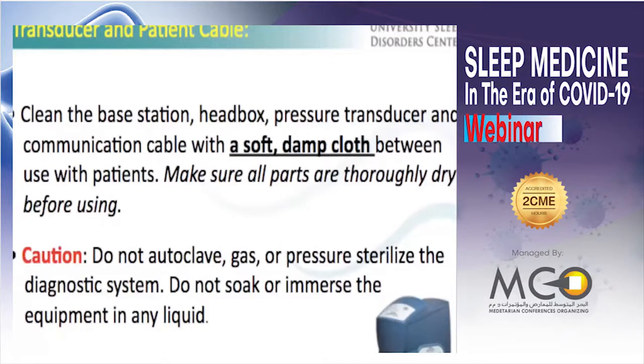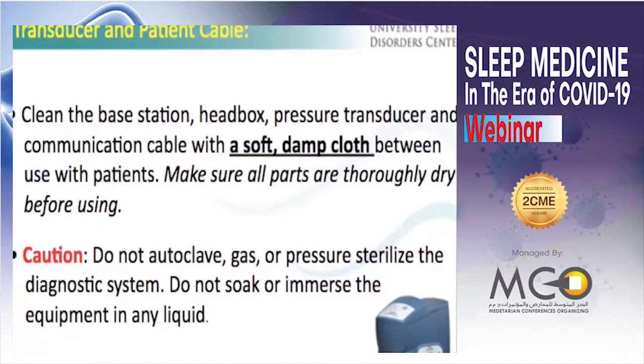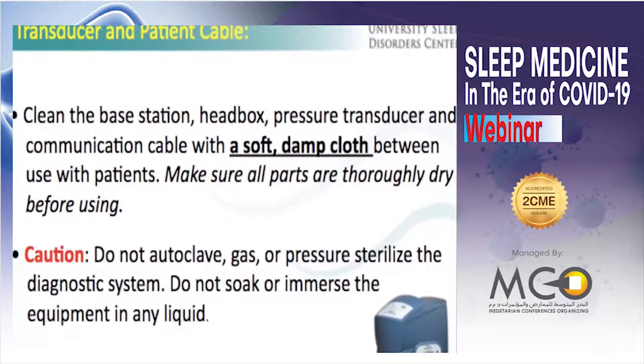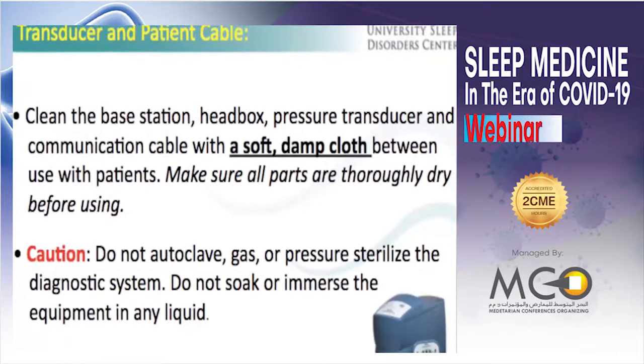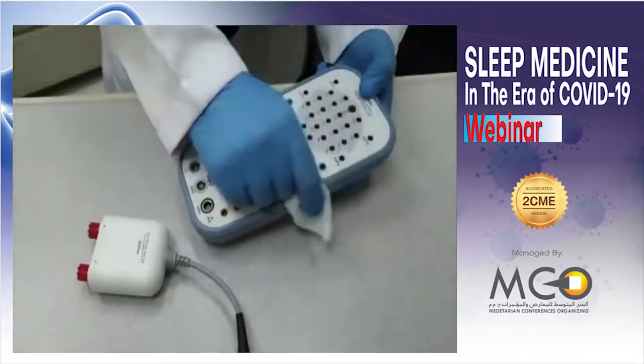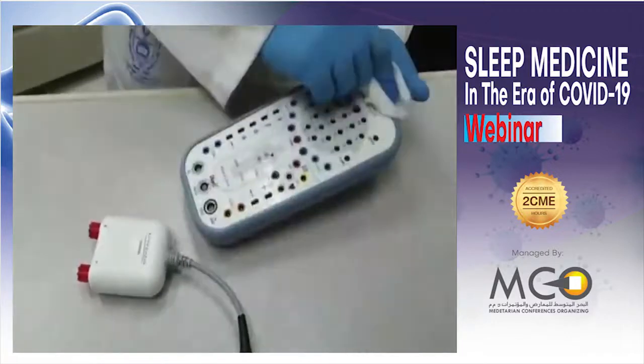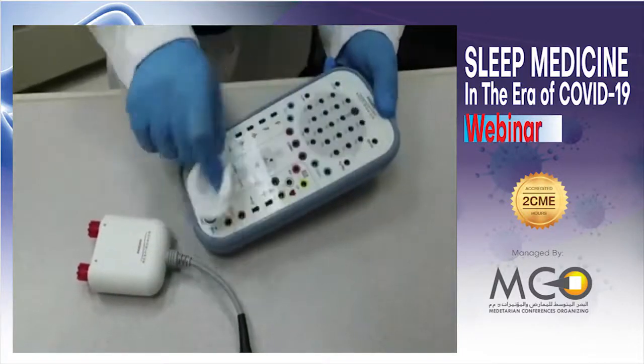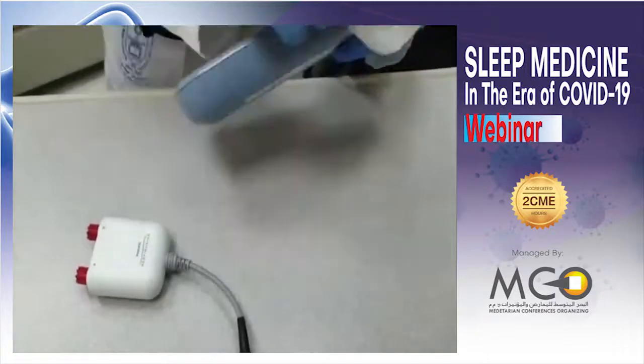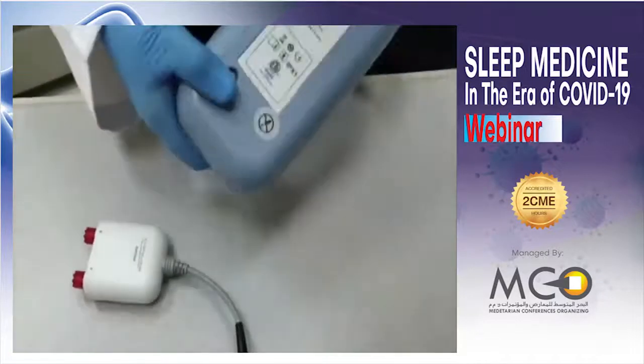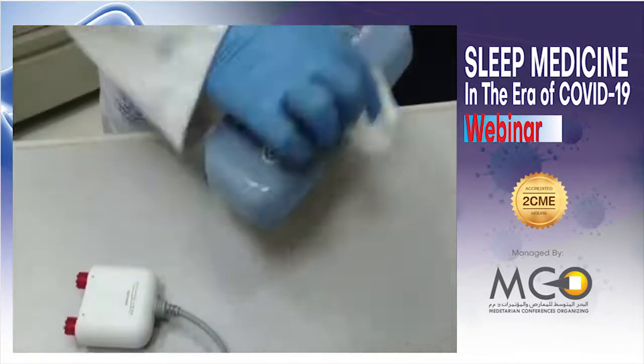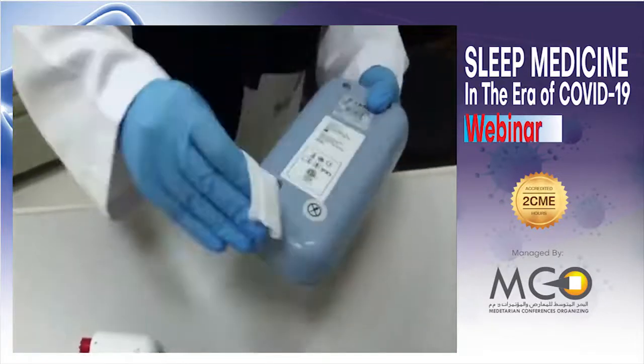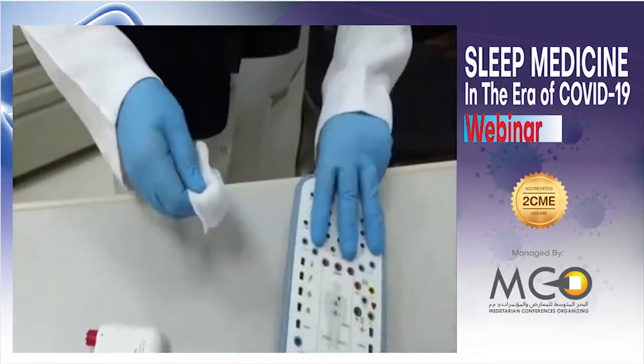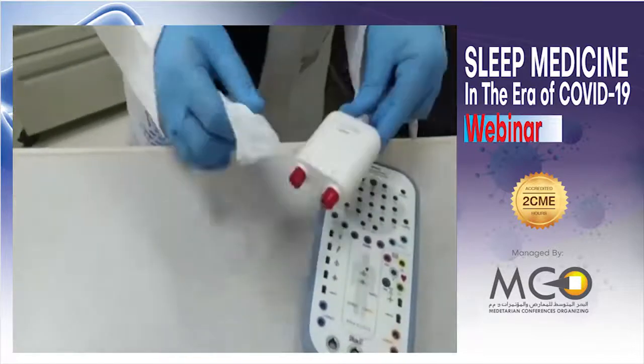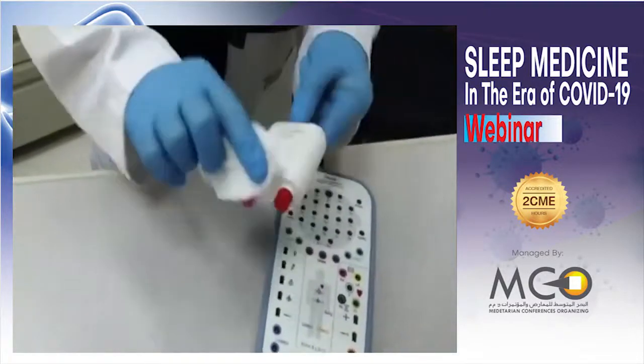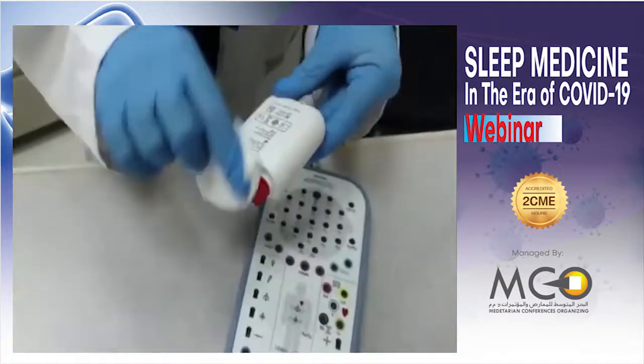First, we will talk about base station, head box, transducer, and patient cable. Clean the base station, head box, transducer, and communication cable with a soft, damp cloth between use with patients. Make sure all parts are thoroughly dry before using. But be careful. Do not autoclave, gas, or sterilize the diagnostic system, and do not soak or immerse the equipment in any liquid.